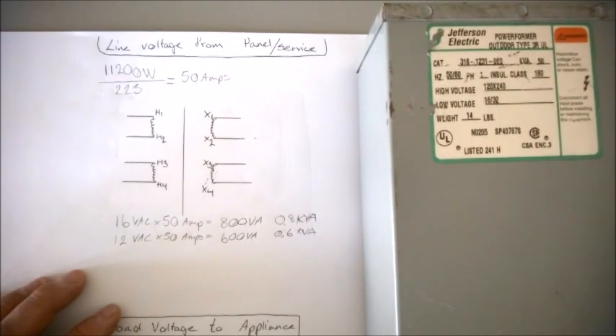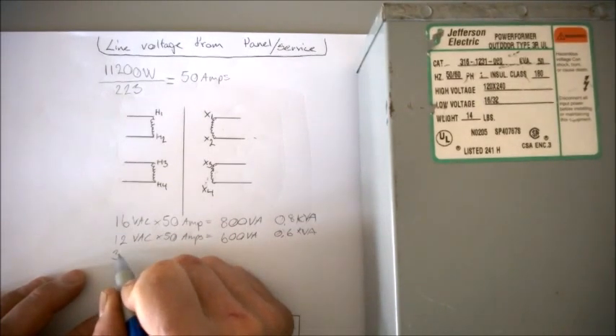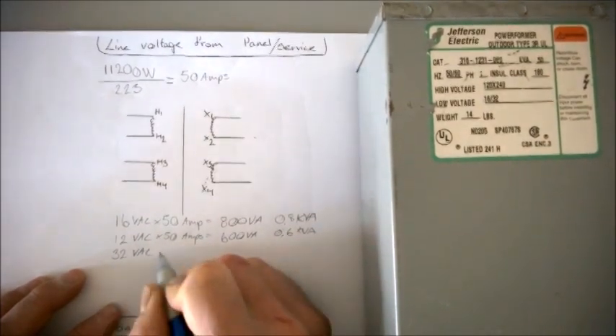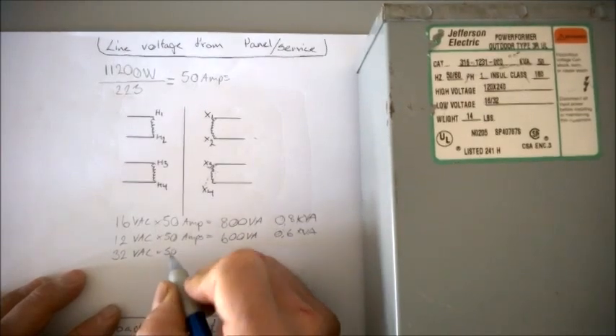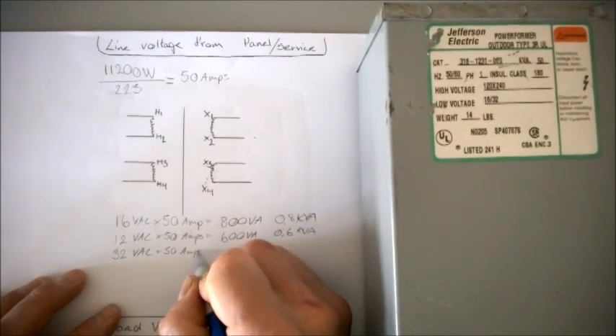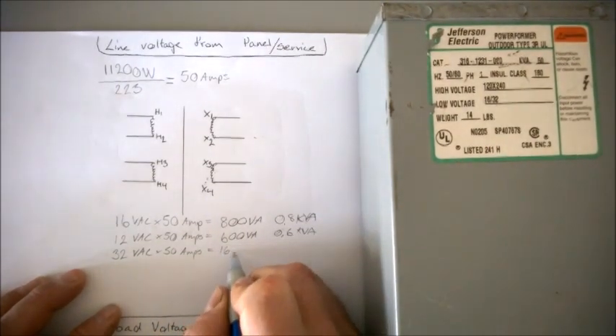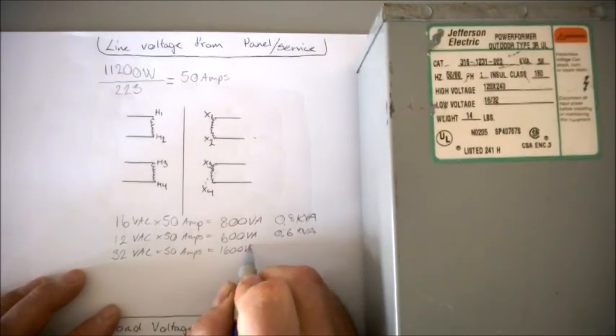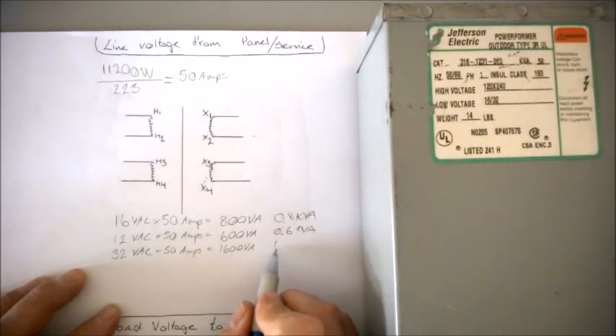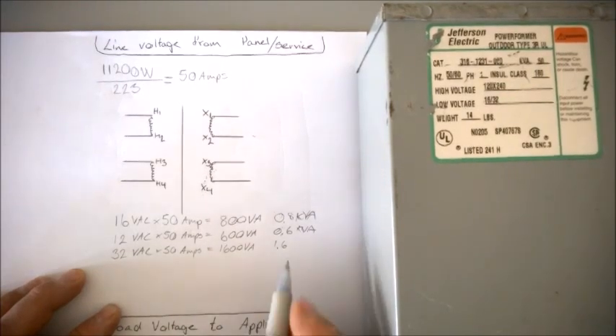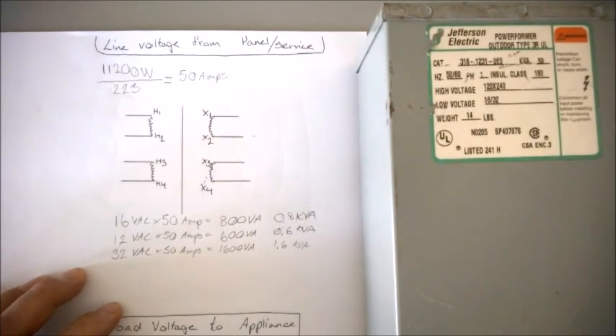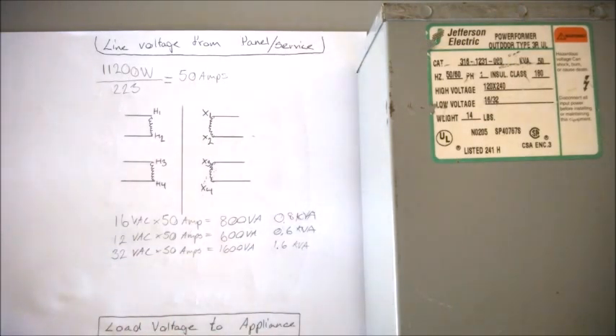That's pretty interesting, but let's go all the way up here to 32 volt AC. Let's see, 50 amps. And now all of a sudden we're up in 1600 VA, 1.6 KVA. And our first matching size to that is a 2.0.